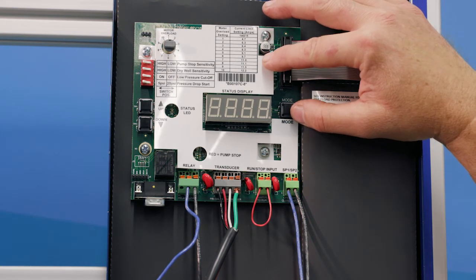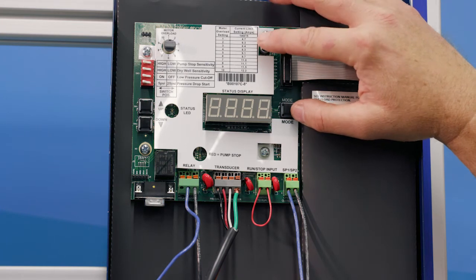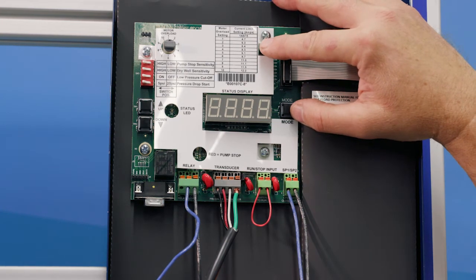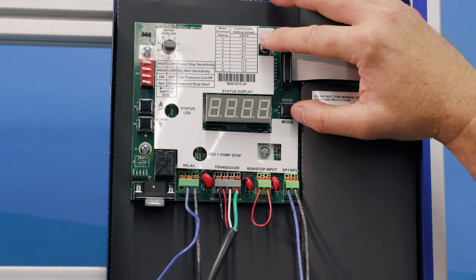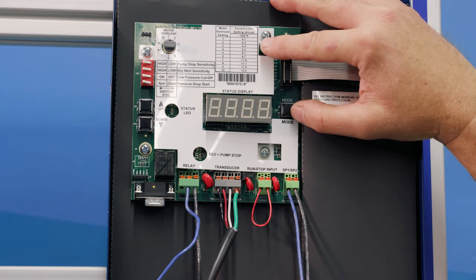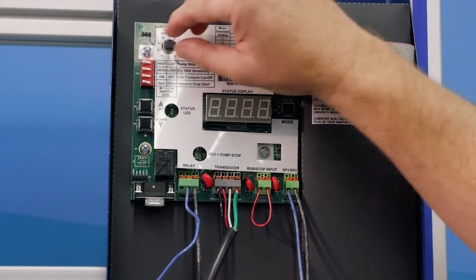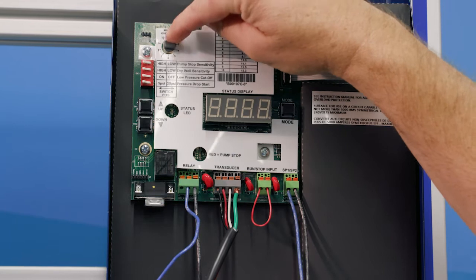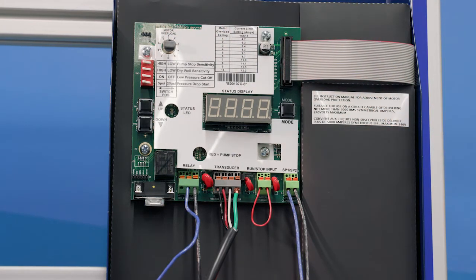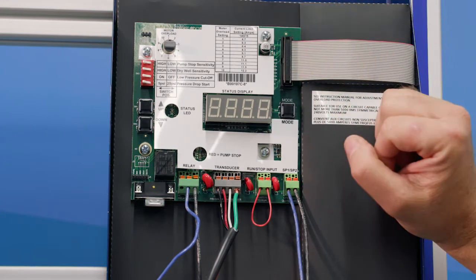So the rule of thumb here with single phase in, single phase out, your 1AS15, is find the closest value. If we look at this chart here, we look at the numbers and find the number that is closest to 4.8. We can see that would be 4.7. So that is setting 1, and we want to make sure this black arrow here is set to number 1. Once you do that, you never have to change it, right? So as long as we got that pump down in there, sort of set it and forget it.